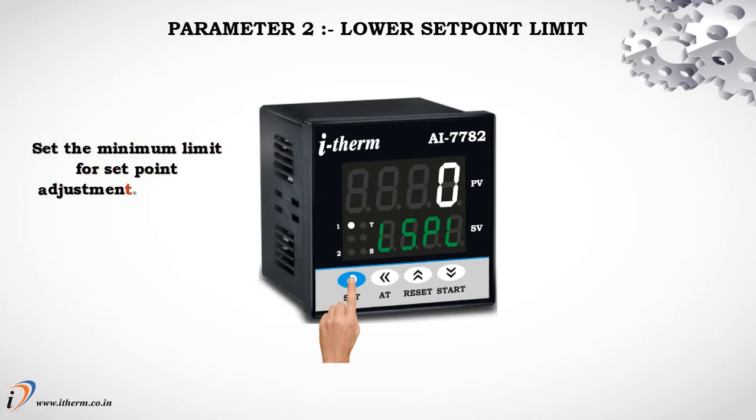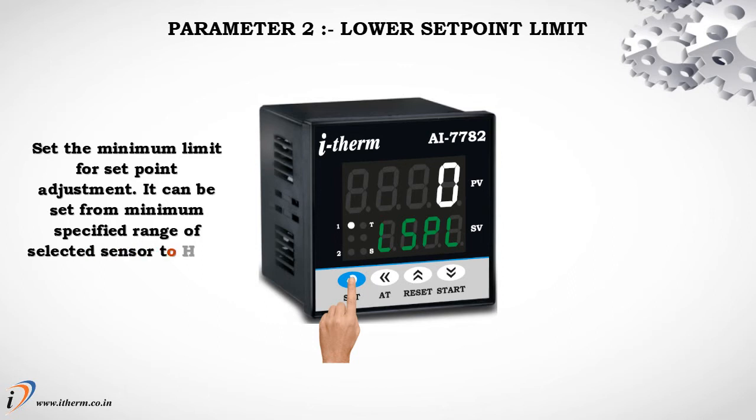Parameter 2, Lower set point limit. Set the minimum limit for set point adjustment. It can be set from the minimum specified range of the selected sensor to the HSPL value. Default LSPL value is 0.